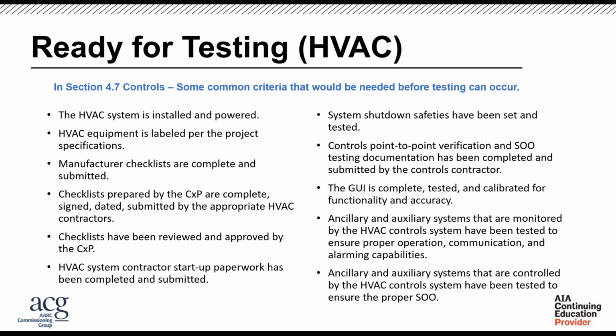So even though we might have had a great design with an amazing sequence of operation, can that control system actually do it? And that's where the point-to-point helps out, where we can see that those sequences actually match what you're asking for in design. The control system is physically able to do it. And like I said, one of the things I find a lot, especially in educational facilities, is room numbers. For some reason, a lot of times the construction room numbers aren't matching the final room numbers that go into the school. And a lot of times the controls are designed based off the construction drawings. So they're referencing room numbers that might not be the same when the building's in operation.